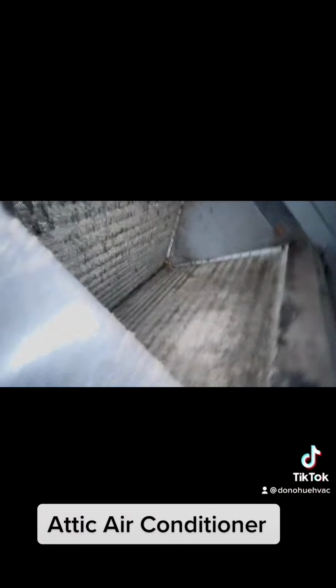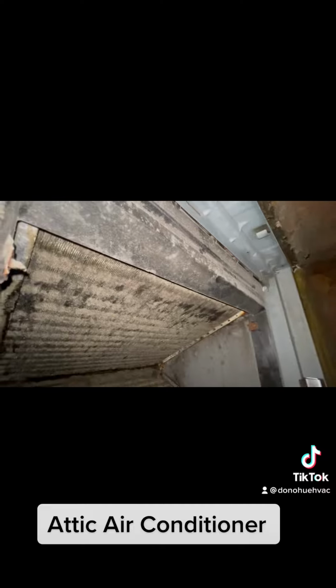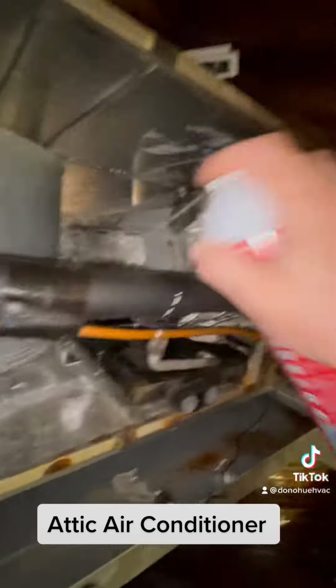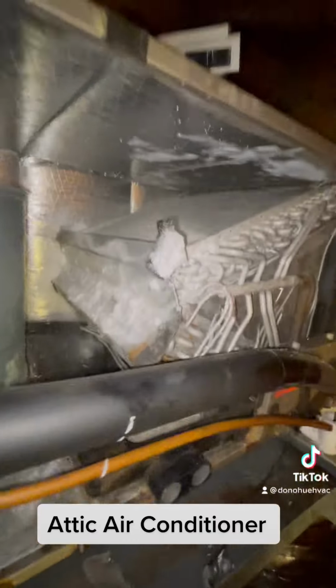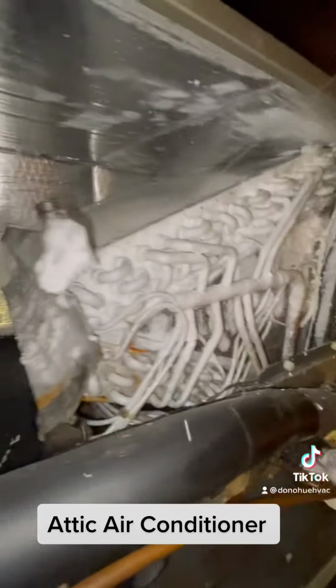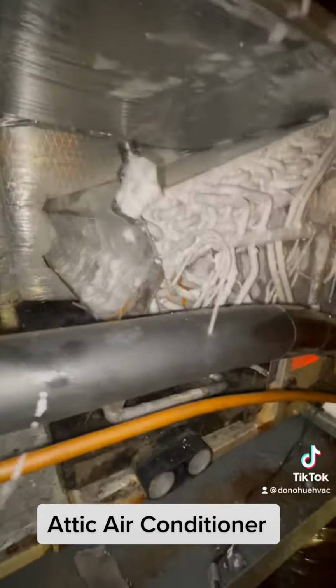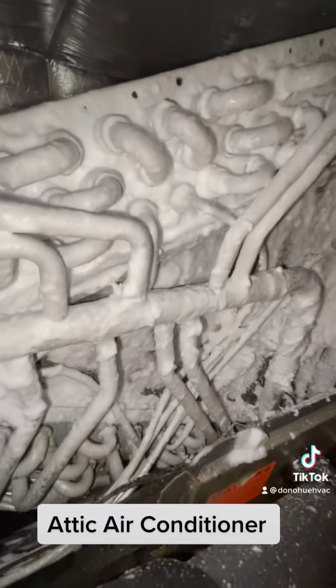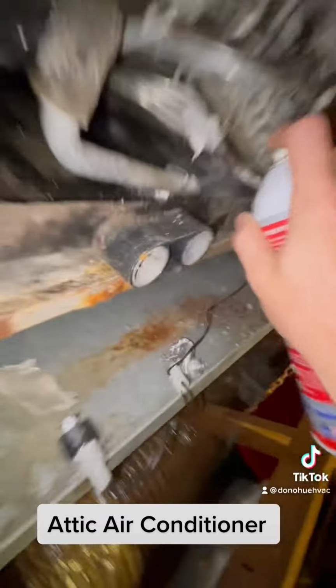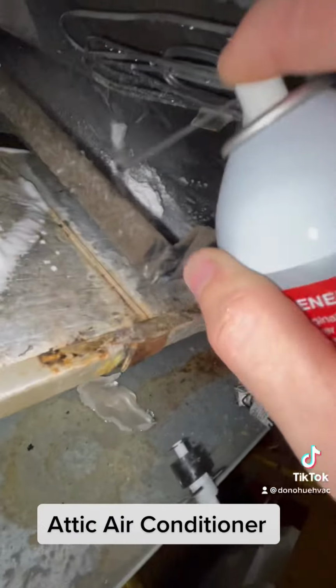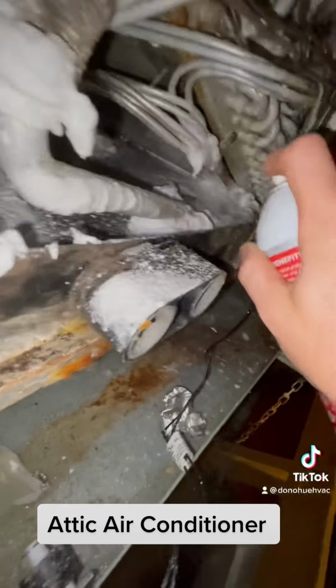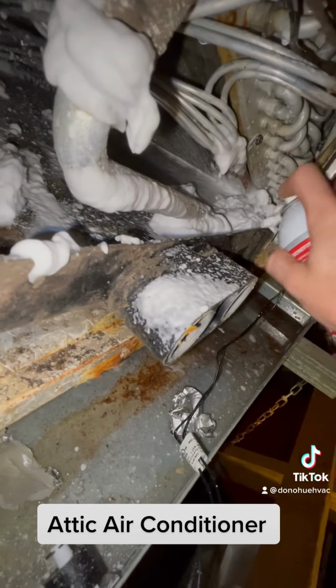The back end of the coil isn't going to be cleaned on a maintenance. If that were to be cleaned, it would have to be pulled and cleaned. But where it's at, I'd just recommend leaving it and not doing anything with it, because to pull that system out of the attic, bring it outside, acid treat it, then clean and wash it, it's just not worth the labor, nor the actual money.